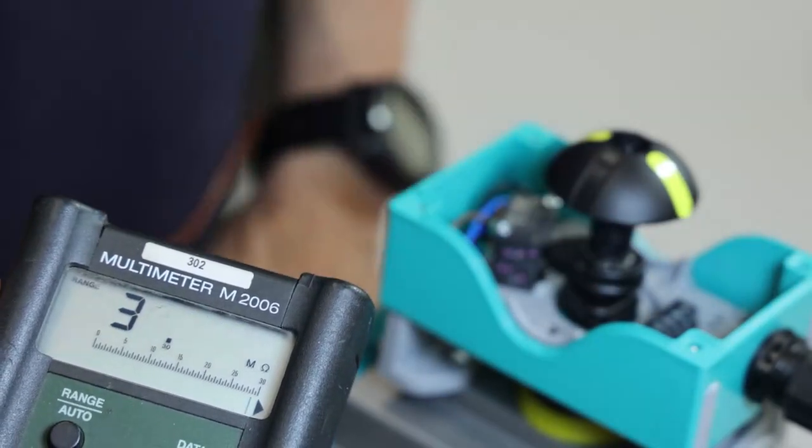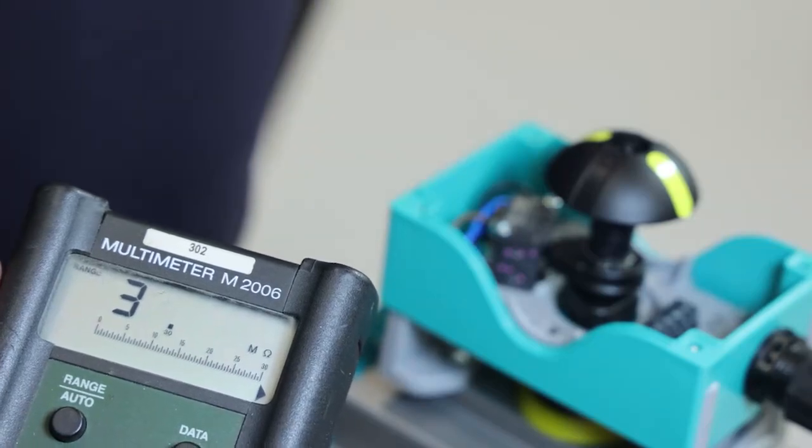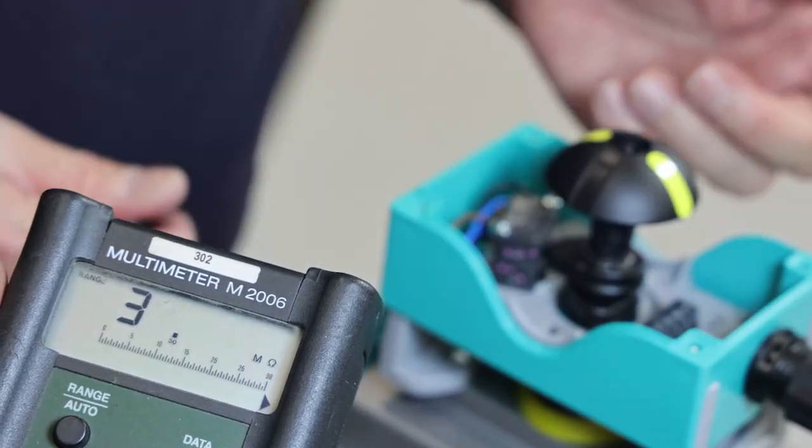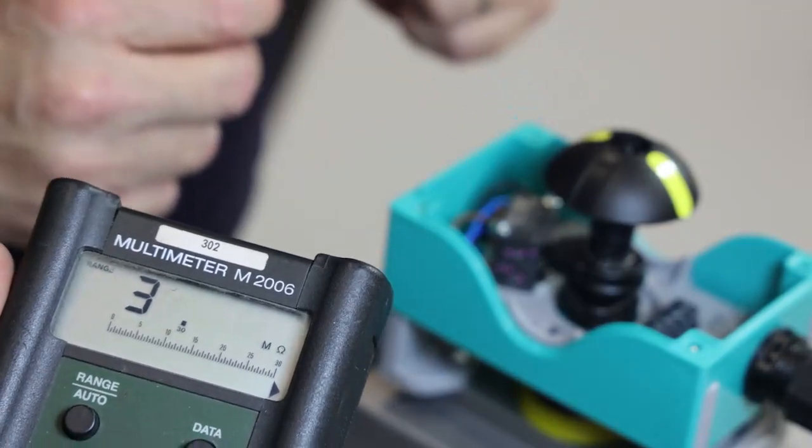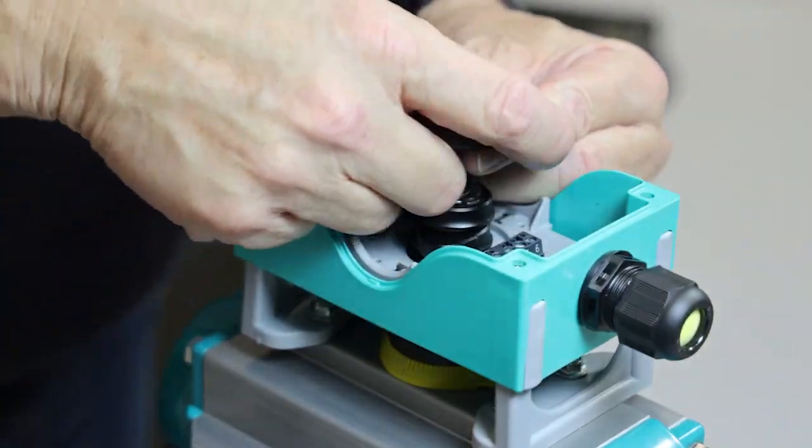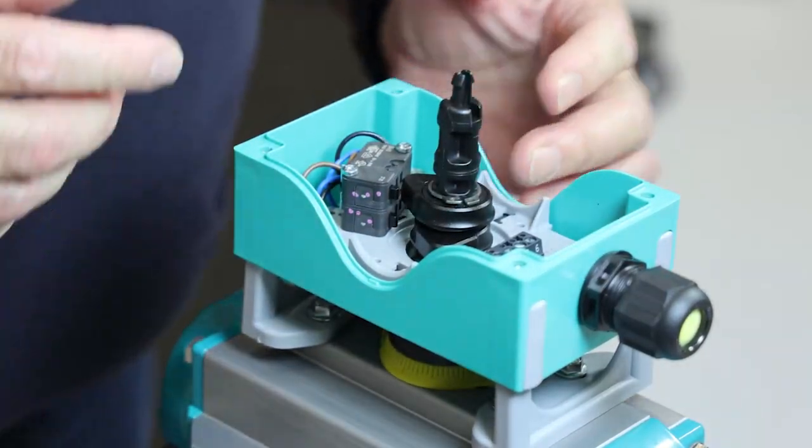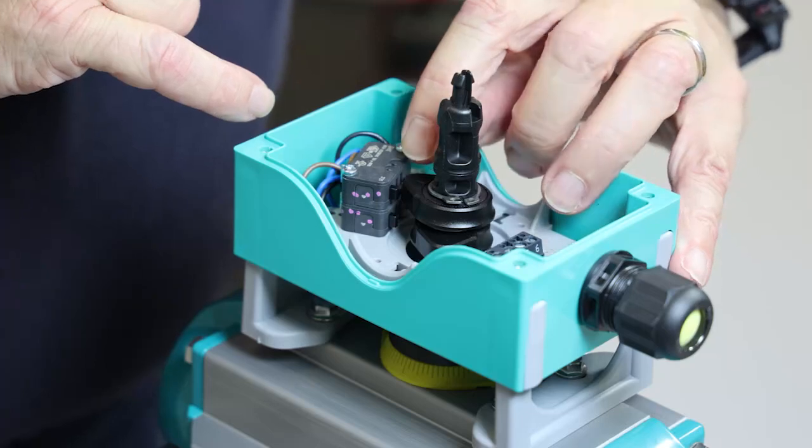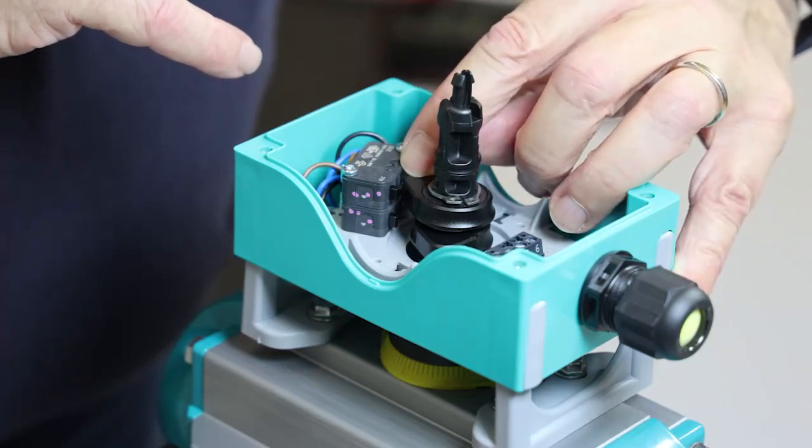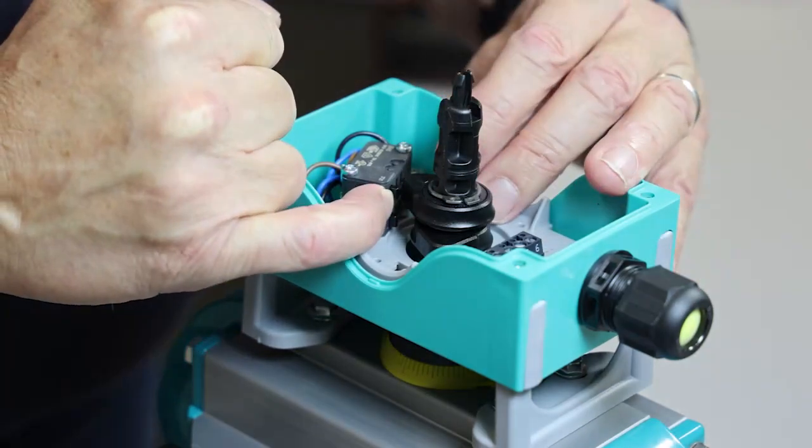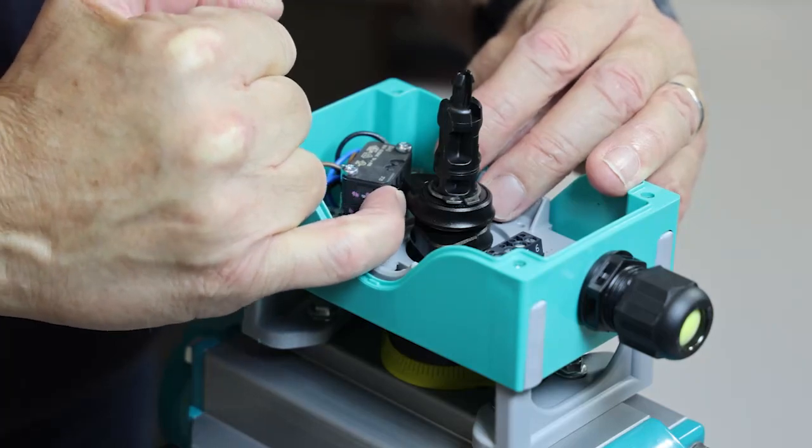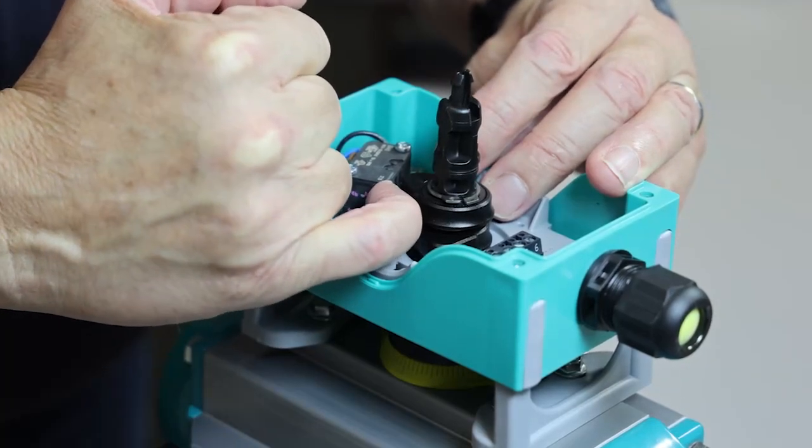Now, in case the signal is not okay, we need to readjust the limit switch cam. To readjust it properly, we remove the position indicator. We see now that the end of the cam is not touching the small cam of the limit switch. It's not activated.